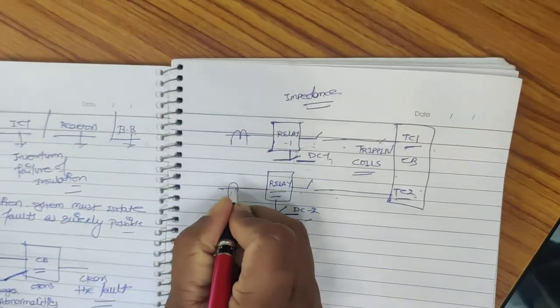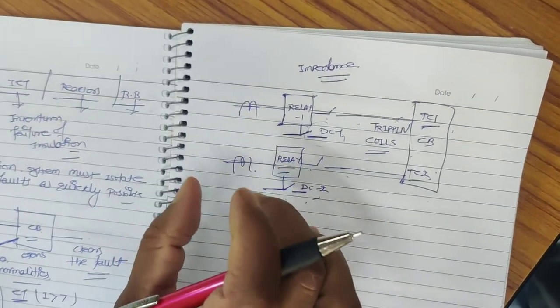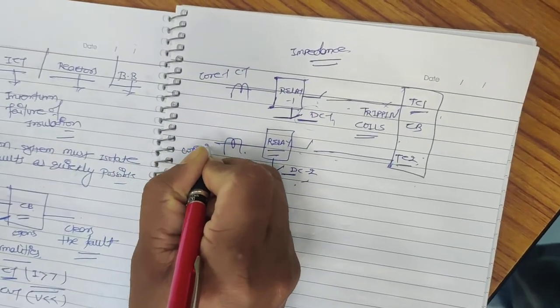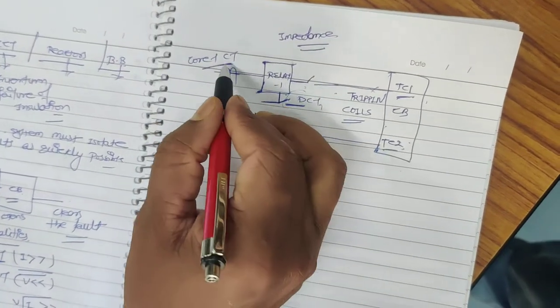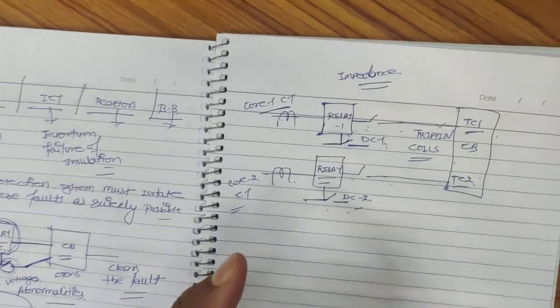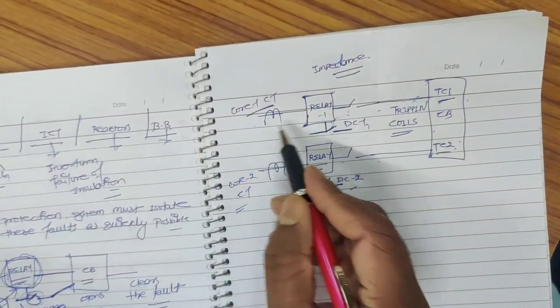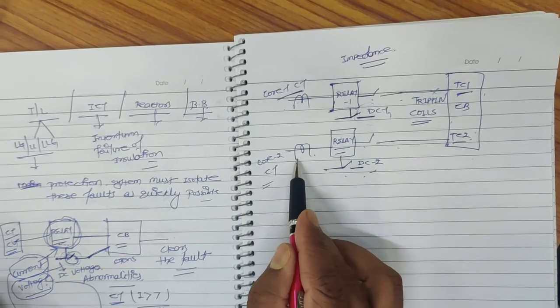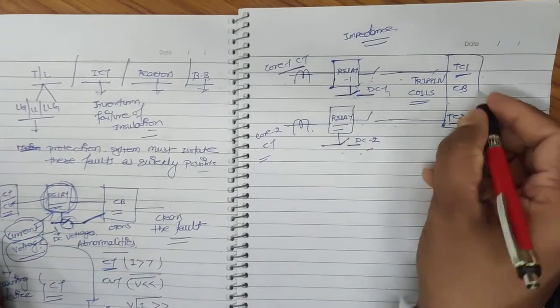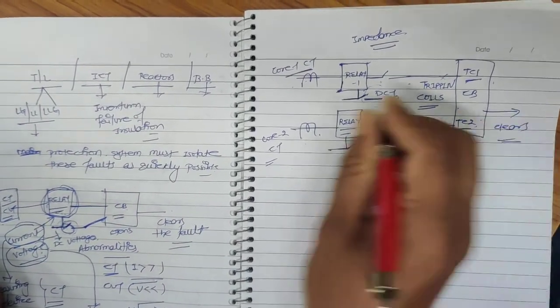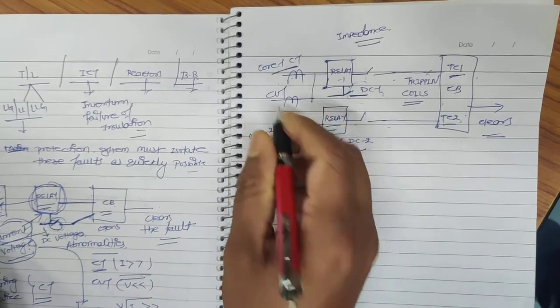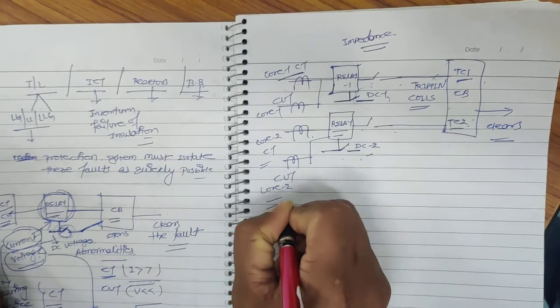Behind the relays, there are CTs and CVTs. We cannot duplicate the CT itself, but we can have two different cores of a single CT — Core 1 and Core 2. If there is any problem in Core 1 of the CT, that path will not detect faults, but Core 2 is healthy. We are assuming only a single failure at a time, not multiple failures. So if Core 1 fails, Core 2 will provide accurate CT measurement, the relay will detect the fault, and from DC Source 2 it will energize Trip Coil 2 and clear the fault. Similarly, for an impedance relay, we will also have CVT Core 1 and CVT Core 2.